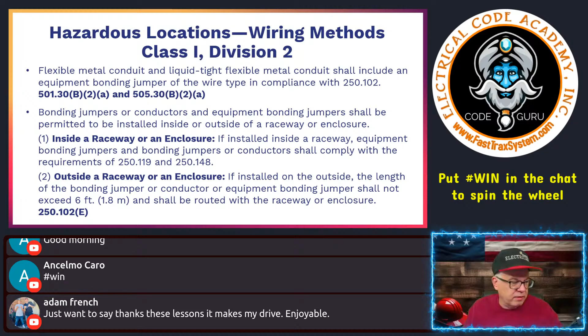I can find it. And that is the continuity. So that is right here. So let's just look at it right here. So that is the continuity of equipment grounding conductors and how they're attached to boxes. Okay. So again, you're going to have raceways that are in these locations. You could have junction boxes. You could have boxes that are hazardous location boxes, explosion-proof boxes. They're metal. You still have to bond them. Okay, still have to do all that. You still have to maintain the integrity of everything tied together.